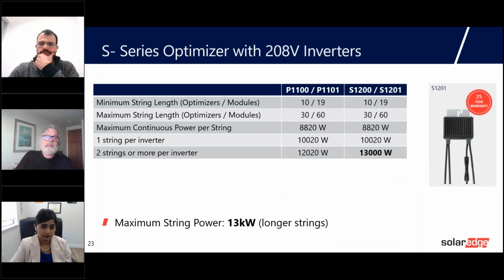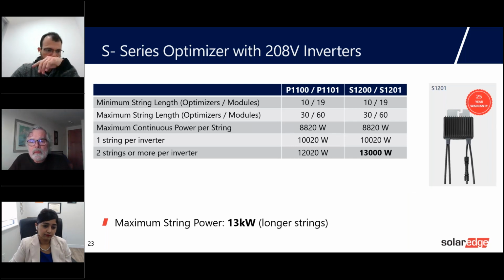Next slide, please. So we have a couple of slides here talking about design rules with the 1100 series and the 1200 series optimizers. Their electrical characteristics on the output side are the same. They limit string current to 18 amps. They each have a maximum output voltage of 80 volts. So the minimum string length guidelines are going to be the same for both of them. Minimum string length would be 10 optimizers in series. And then one of those could have a single module. So we could have 10 optimizers, 19 modules per string.